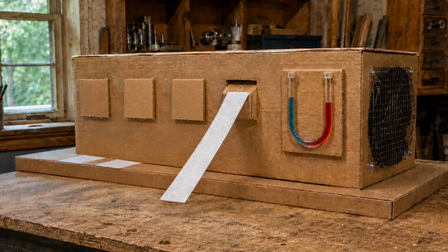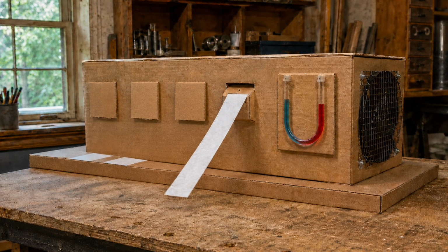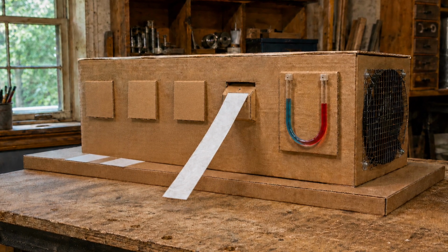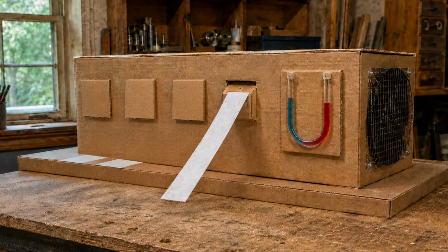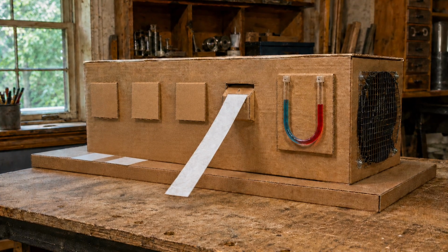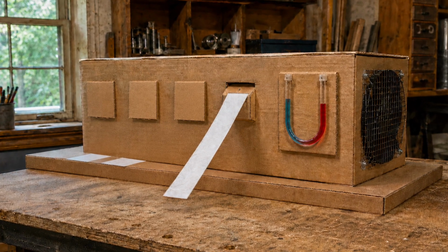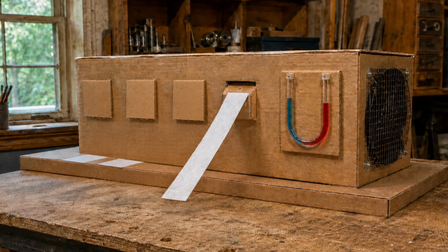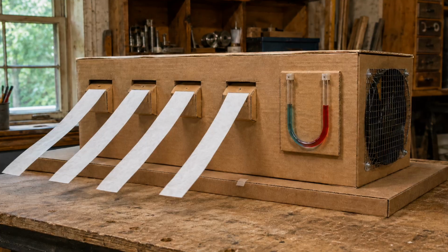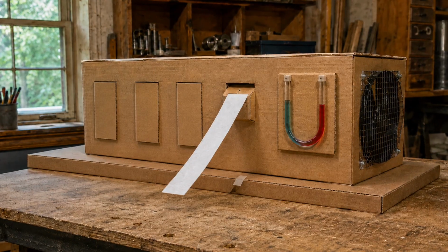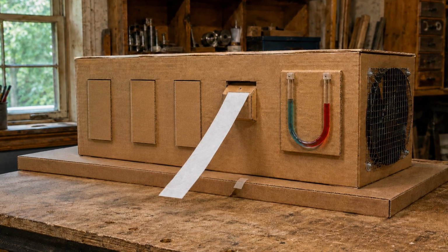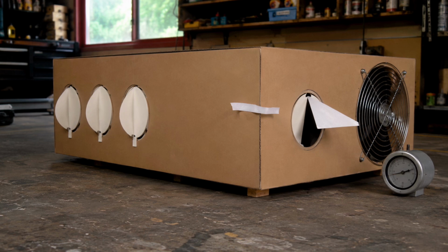The sound of the fan may change, but sound alone does not tell us how much electricity it is using or how hard its motor is working. The pressure gauge tells us what we can prove here. The restriction in front of the fan has increased. The 4-room system did not become an efficient 1-room system. It became a 4-outlet box with 3 blocked exits.